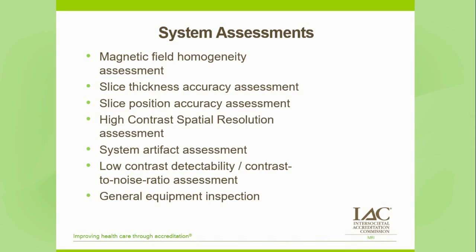What about the general equipment inspection? This probably includes an assessment of the radio frequency shielding, the monitor — what else should be evaluated? This is the technologist gut check, really. What I always tell technologists is that when you walk into your room and walk around your scanner, you know how things are supposed to be.